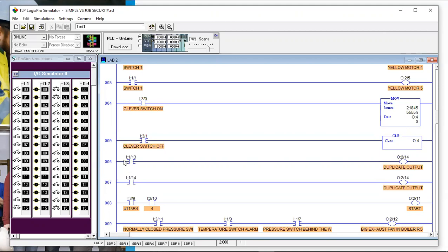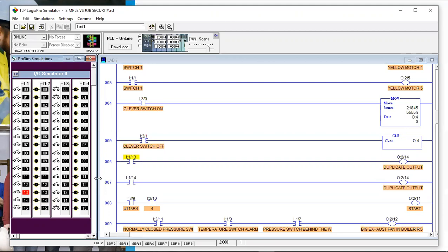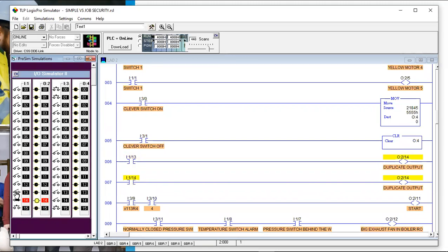Input 1-1-3 is this switch. Let's see if it works. It doesn't. The program says: if 1-1-3 is true, turn on 2-1-4 — and it didn't work. Let's try the other one: if we turn on input 1-1-4, turn on 2-1-4 — that does work. But if we try the first switch again — nope. The reason is they're both referring to output 2-1-4, and in this case the last one wins — whether it's on or off, that last rung overwrites that bit.